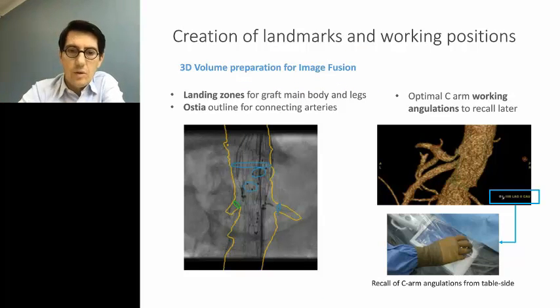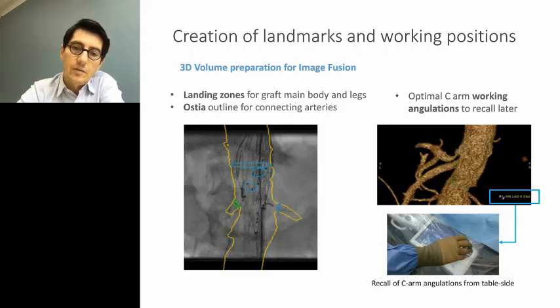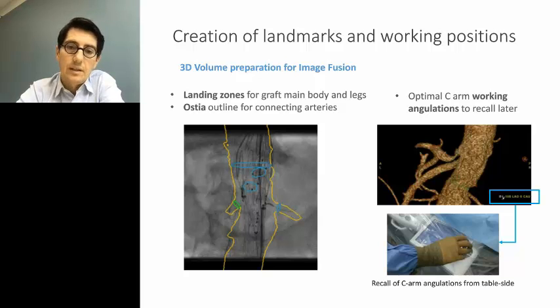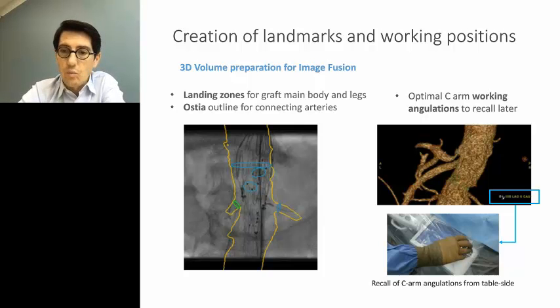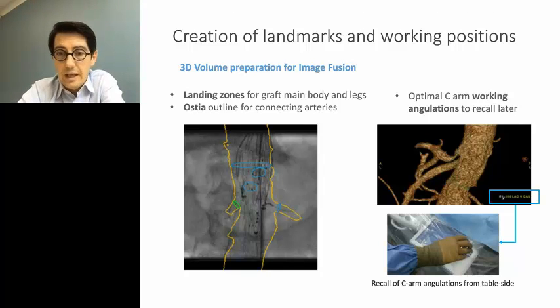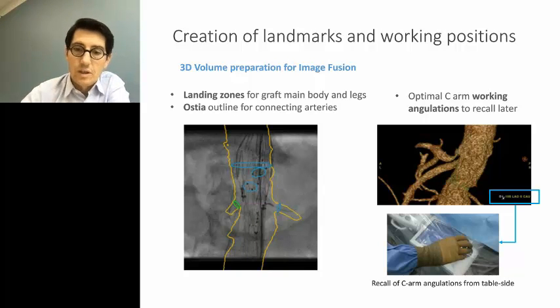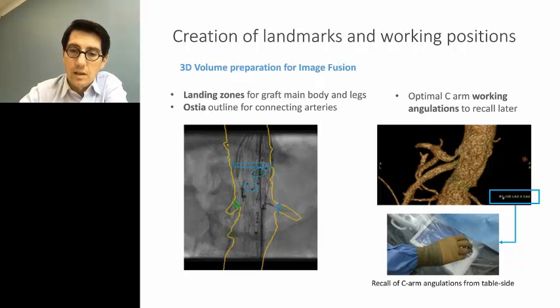Once the endograft is sized, you position the various landmarks. The most proximal blue circle in the aorta represents the top of the stent graft, and you can see the origin of the visceral vessels and renal arteries with the contour of the aortic lumen. We store all the various working positions — you have preset positions such as proximal seal or distal seal, and you can add as many positions as you want that can be recalled from tableside on the day of procedure. By recalling one position, the gantry will automatically move to that best working position, which is very useful when performing the case.